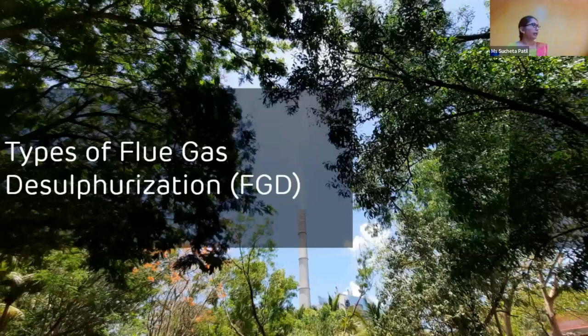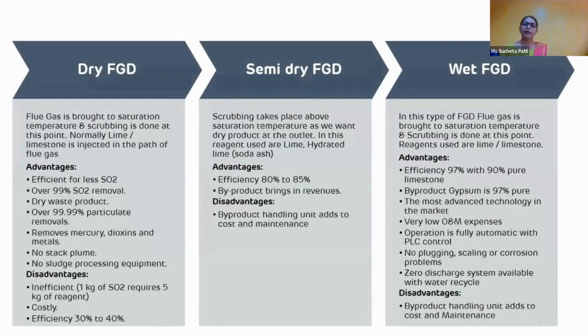So we discussed yesterday and today also what are the different types of flue gas desulfurization systems. There are mainly three types of flue gas desulfurization systems, which are dry FGD, where flue gas is brought to saturation temperature and scrubbing is done at this point. Normally, limestone is injected in the path of the flue gas, and this type of FGD has some advantages. It is efficient for less sulfur dioxide. Also, 99% SO2 is removed through this system. Then dry waste product, then over 99.99% particulate removal. Also, it removes mercury, dioxins, and metals. And there is no stack plume, no sludge processing equipment is required.